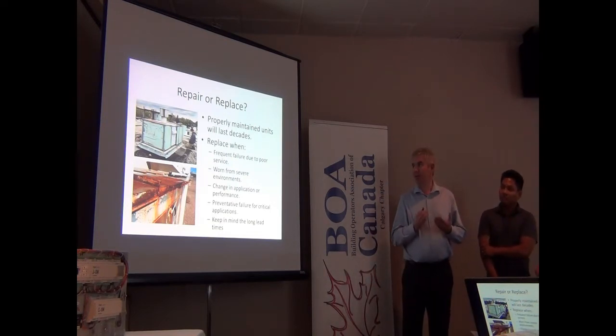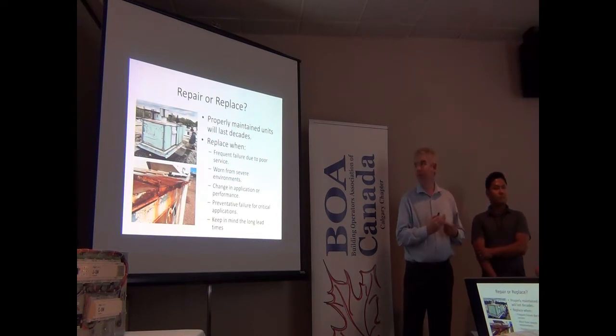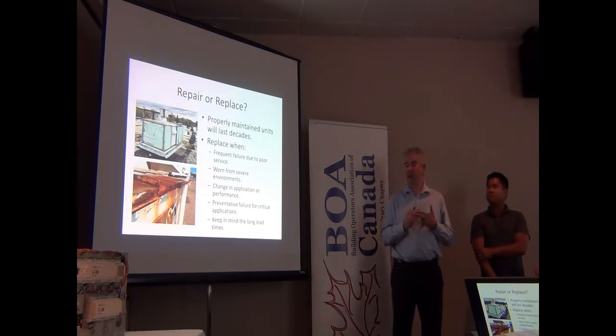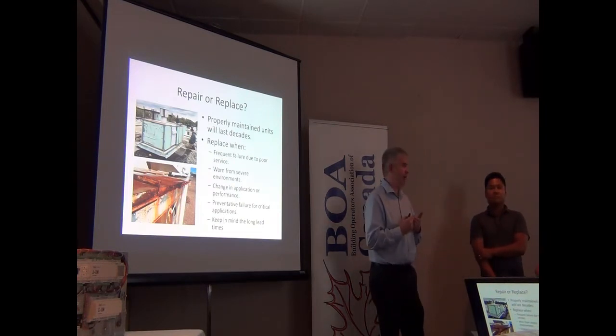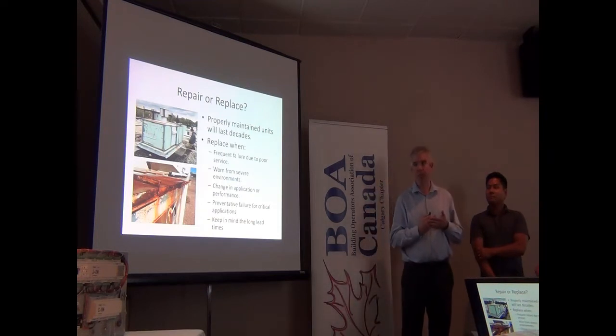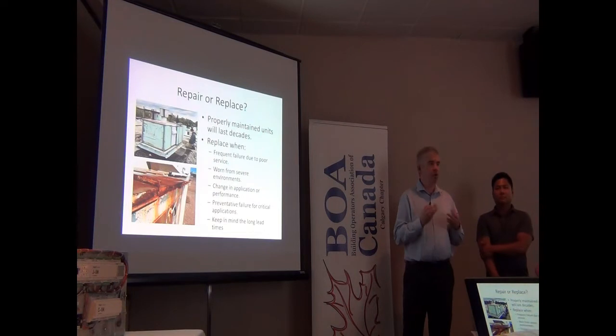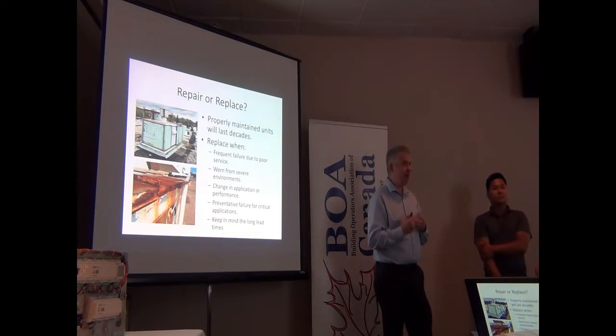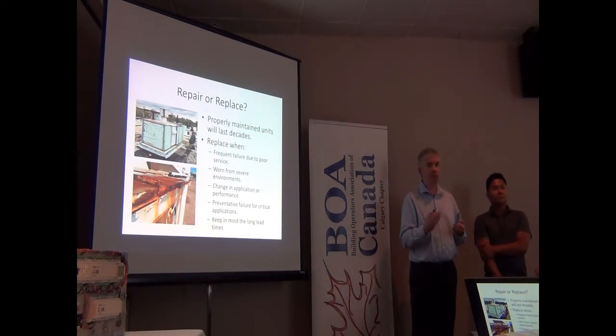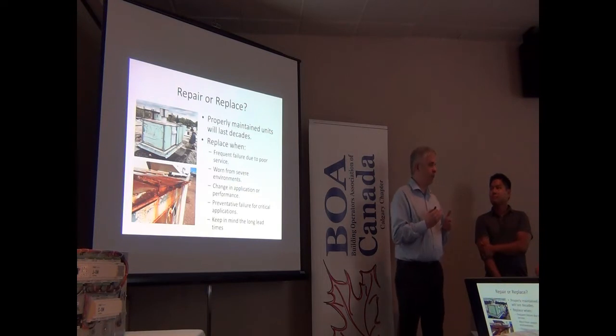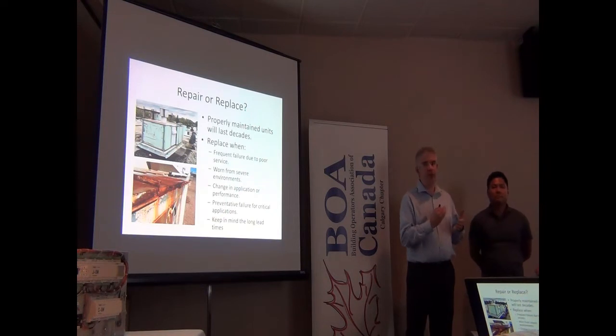So the considerations are, again, what type of components you have, what type of service it's actually in, and then looking at how things are changing. Aside from just general age, we might want to change it because we have a change in application. There are new tenants in a building space, the space is being repurposed, or the space is being expanded. Do you have a critical application where something absolutely has to work in this space? Failure is not an option. We might look at it and say we're approaching what would be an appropriate lifetime for the unit. Maybe it's preventative to replace it even if failure isn't imminent.